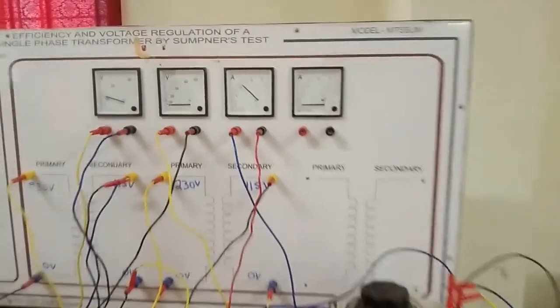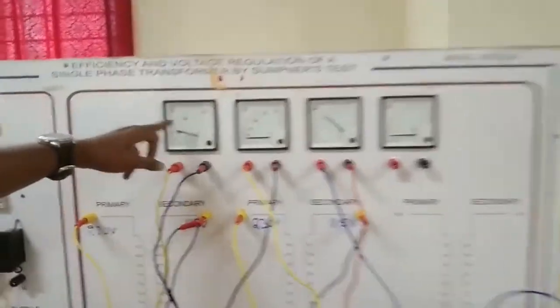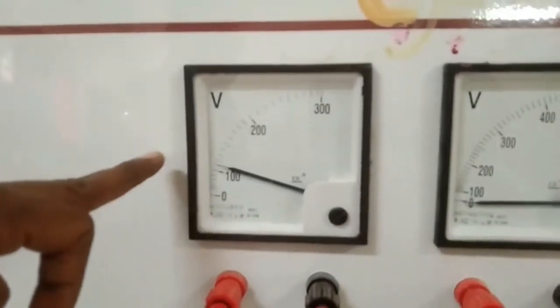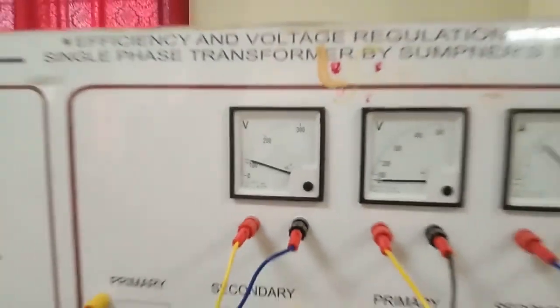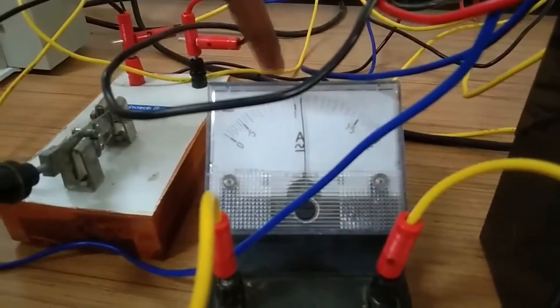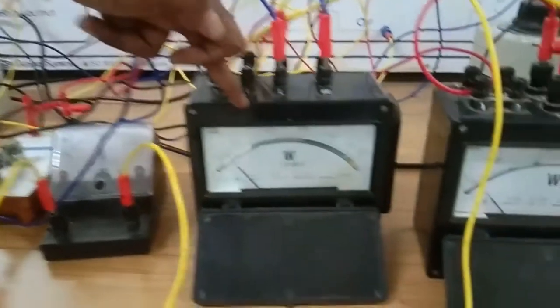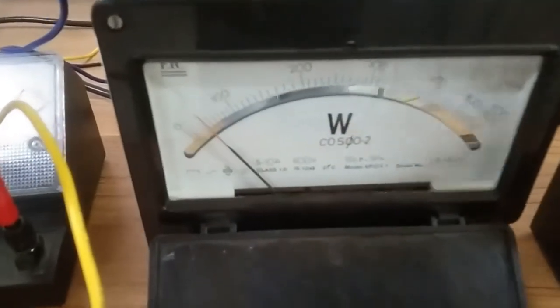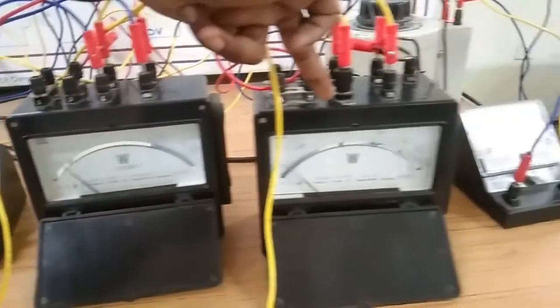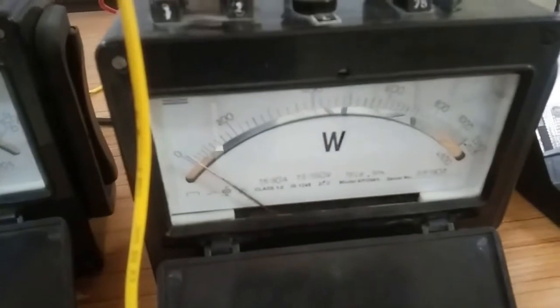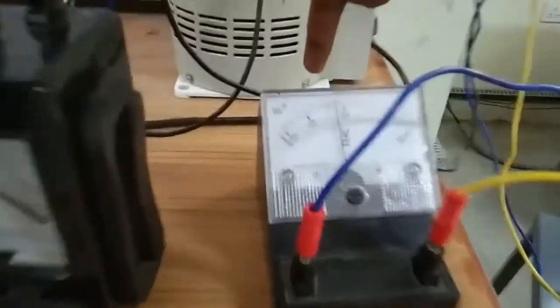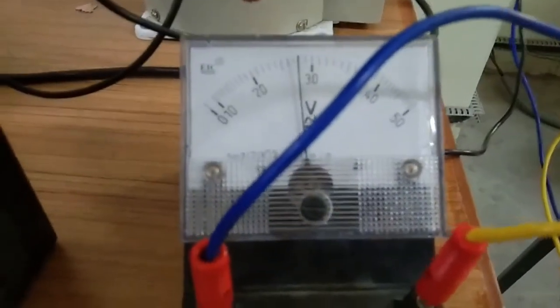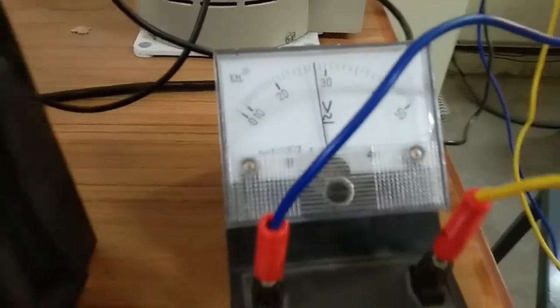So first meter is voltmeter V1, 115 volts. Next, ammeter, 1.05 amperes, and W1, the iron losses of both the transformers, near about 50 watts, and W2, the copper losses, near about 35 watts, and V2, the short circuit voltage, will be near about 28 volts. Okay, so after observing all the meter readings, what we need to do is find the losses.